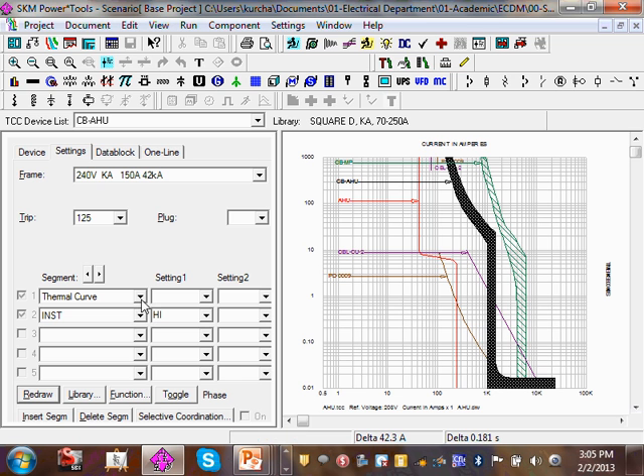Now I want you to watch right here, instantaneous. Now it's set at high. It's set at high, which says if I have a short circuit condition right here, don't trip, don't trip, don't trip, and allow it to sit, like, what is it? These are 20 seconds. Wait 20 seconds before you trip.